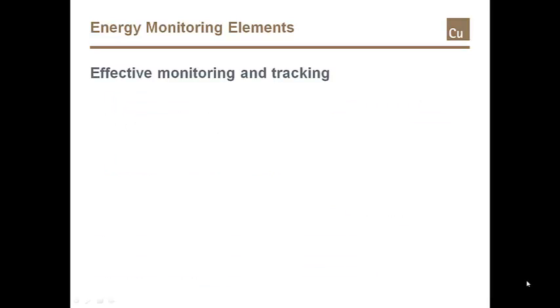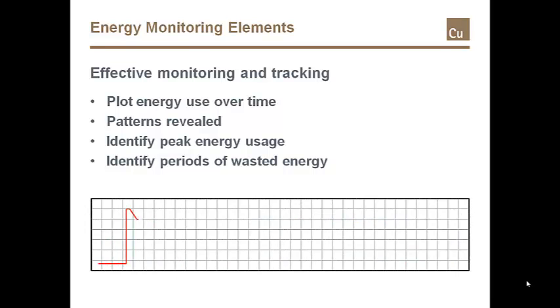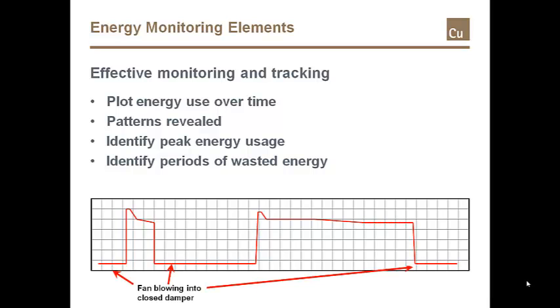Many facilities actively monitor processes using SCADA or other systems. This monitoring facilitates the plotting of energy use over time that may reveal patterns. Peak usage and periods of wasted energy may be identified. In this example, energy use over time reveals that this process, a combustion air fan, pushes air against a closed damper for long periods of time.